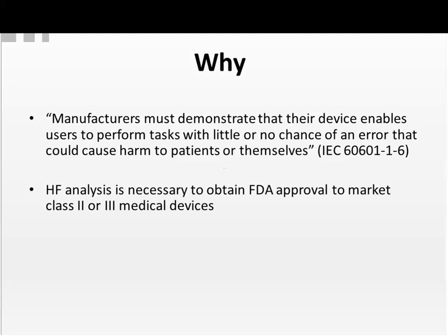So the IEC 60601, which is the electrical safety standard, discusses human factors. And another point, to get approval to market a Class 2 or Class 3 medical device, as part of the submission, there must be a human factors analysis.